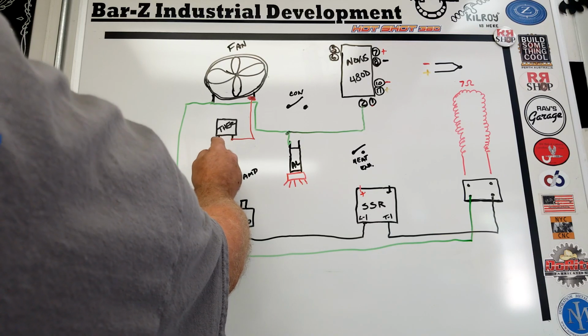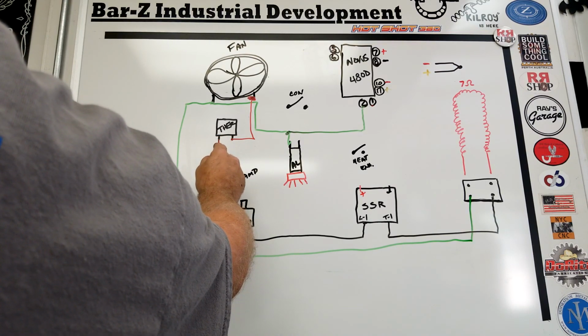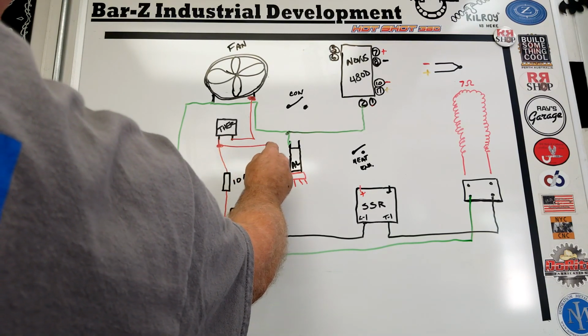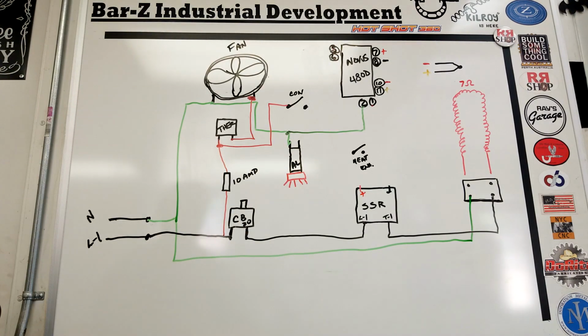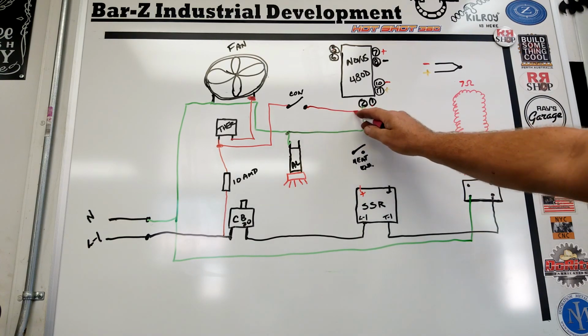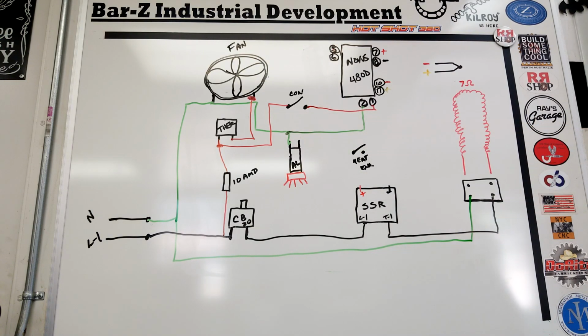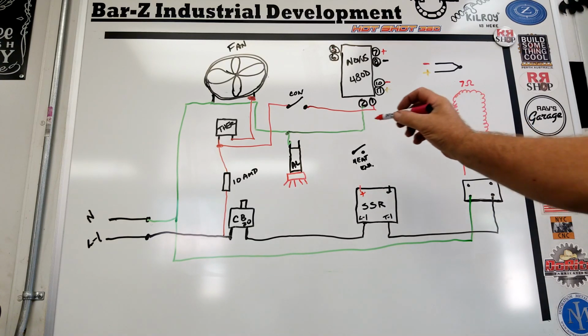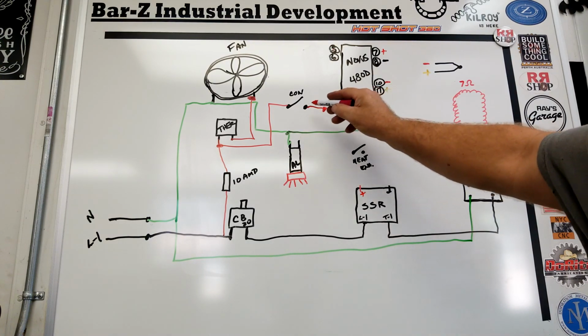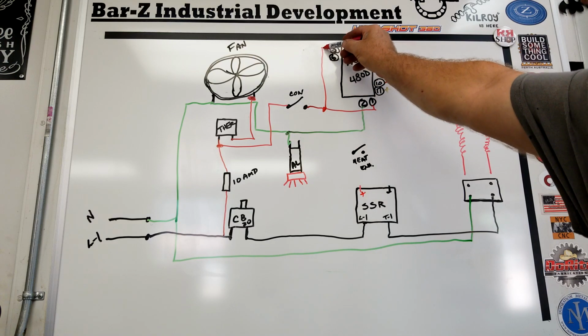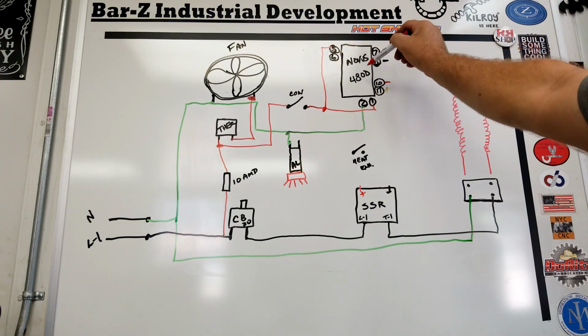Out of this connection, you make a double connection here, and you come out and you go up to a control switch, which is in the cover of your Hotshot, which is just a single pole, single throw switch. From there, you come out of there, go to terminal 1 on your Novus. As soon as you hit that control switch, Novus boots up. You need to make a small jumper out of that switch. Come on up to terminal number 5. This is your switch gear within the Novus.